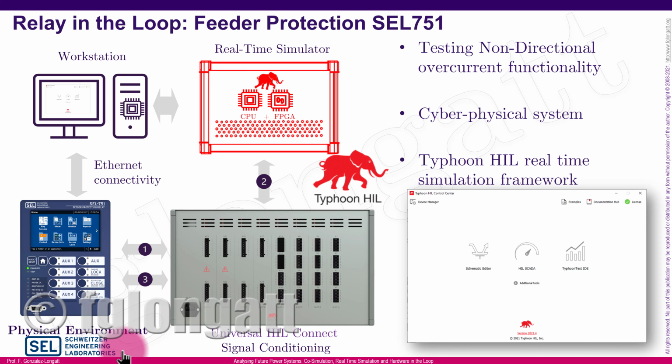In this case, I am presenting one study case related to the feeder protection relay, the SEL 751. To be honest, this scene that I will show you in a few minutes is basically one of the labs that my students take. They go to the lab and test the non-directional overcurrent functionality of the SEL 751, using this cyber-physical approach using power hardware in the loop, okay?